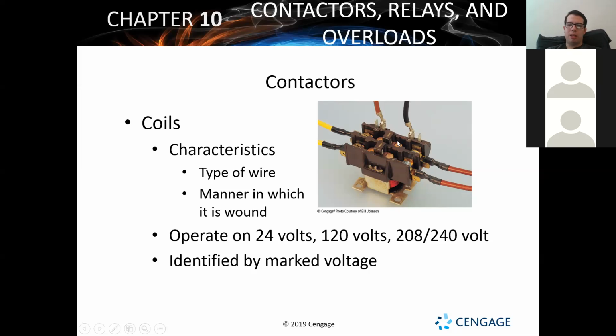But for residential, they cost like $20 at most. And yeah, it just makes way more sense to just buy a new one. It's cheaper, it's easier. You could probably find this little contact end, that coil and all that. But the time it would take to take it apart, take it off the old contactor, put the new part on the old contactor, reinstall it, and connect all your wires again, you'd have wasted enough time that it's like, well, I could have just taken all the wires off and put in a brand new part for $10 more parts cost, but $20, 20 minutes less of labor time.